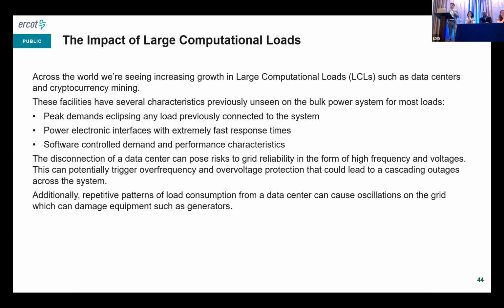If you're from a utility and you're not studying data center interconnections on your system right now from a reliability impact standpoint, you should be. You need to respond to the NERC level 3 alert, and you're going to have to explain, 'no, I don't have a study,' and why. So standards are coming—we're targeting approval by the end of the year for Project 2026-02 for the NERC board, and then it'll go to FERC. Just keep that in mind.